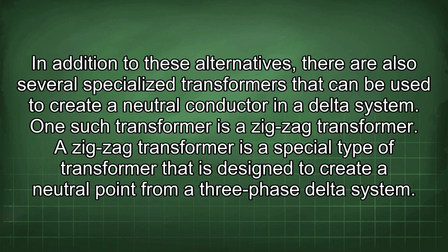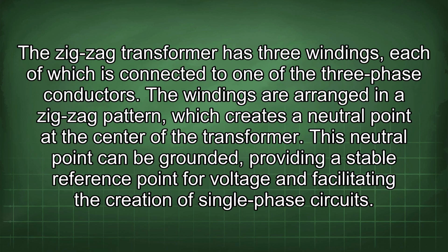In addition to these alternatives, there are also several specialized transformers that can be used to create a neutral conductor in a delta system. One such transformer is a zigzag transformer. A zigzag transformer is a special type of transformer that is designed to create a neutral point from a three-phase delta system. The zigzag transformer has three windings, each of which is connected to one of the three-phase conductors. The windings are arranged in a zigzag pattern, which creates a neutral point at the center of the transformer. This neutral point can be grounded, providing a stable reference point for voltage and facilitating the creation of single-phase circuits.